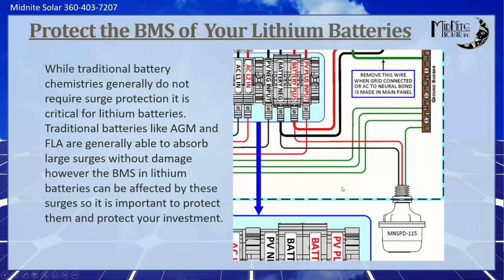And batteries, we talked about that a little bit, but historically we've always said that, hey, a lead acid battery is a great surge arrestor. I've seen lightning strikes where the batteries are actually physically blown apart, but it didn't damage a lot of the stuff because the battery absorbed it. But now with the lithium batteries and what we call a BMS, a battery management system, protecting that is pretty important because those things aren't cheap.